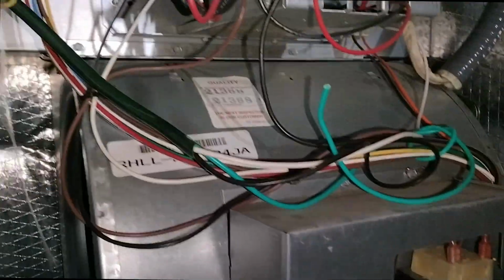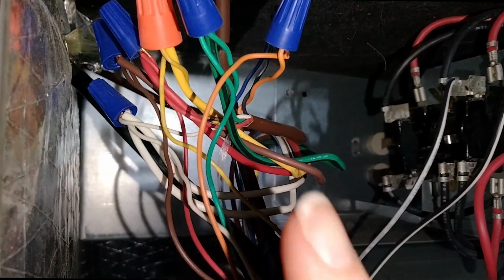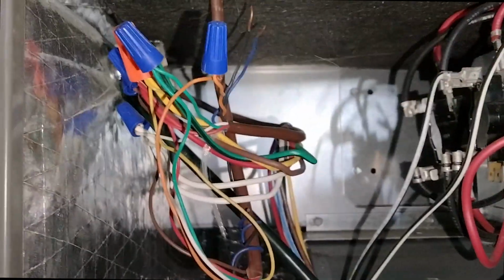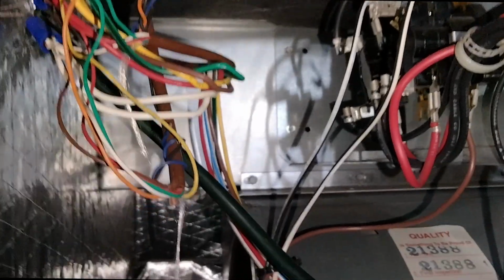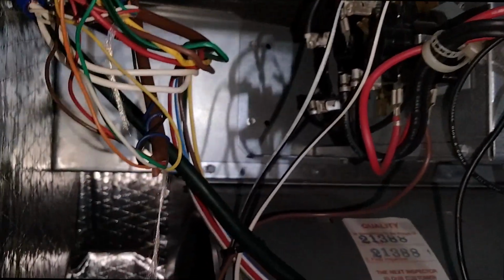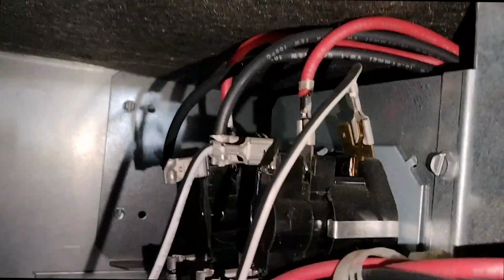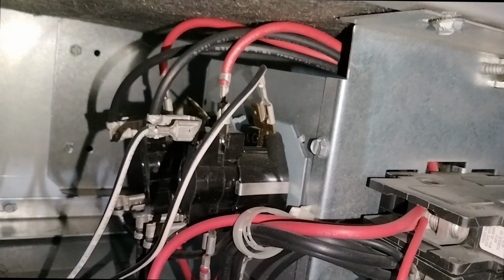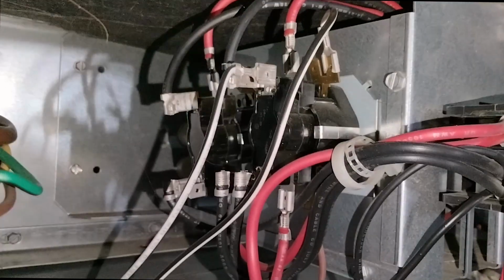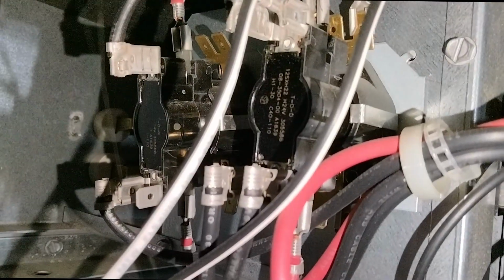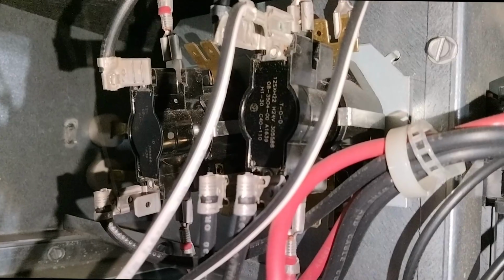Now, your thermostat wires are going to be coming in. It's those little tiny small wires, really thin, small gauge wire like this. That's going to be the call from the thermostat coming in, like we spoke about, that's going to connect to the power of the unit. That's basically sending the 24 volts in on your low side power. On your sequencers, you can see your low side voltage here on the bottom. This is your 24 volts here. See if I can get a little more light on that. These bottom legs here are your 24 volts. There's going to be a delay on startup depending on your timing for your sequencer, which again, if you reference my sequencers video, it talks about what all these timings mean.